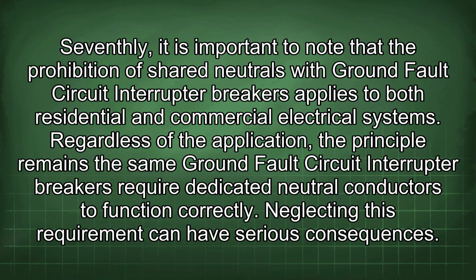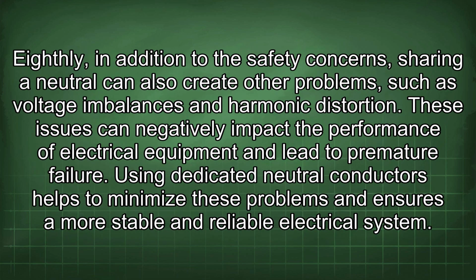Neglecting this requirement can have serious consequences. Eighthly, in addition to the safety concerns, sharing a neutral can also create other problems such as voltage imbalances and harmonic distortion. These issues can negatively impact the performance of electrical equipment and lead to premature failure. Using dedicated neutral conductors helps to minimize these problems and ensures a more stable and reliable electrical system.